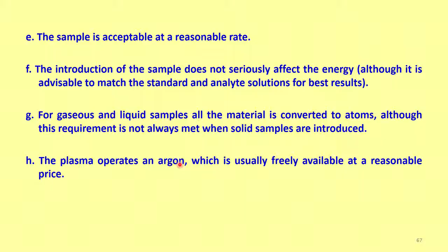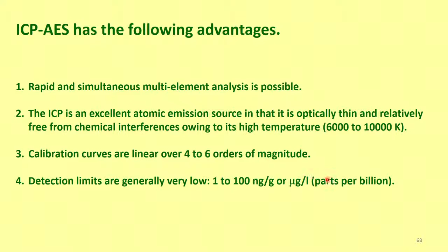So, it has the advantages. One is rapid and simultaneous multi-element analysis. It is an excellent source of atomic emission, in that it is optically thin. Calibration curves are linear over 4 to 6 orders of magnitude. Detection limits are very low, 1 to 100 nanograms or micrograms per liter, that is parts per billion, and it is suitable for analytes at all concentrations from trace to major levels. Accuracy and precision are very good.